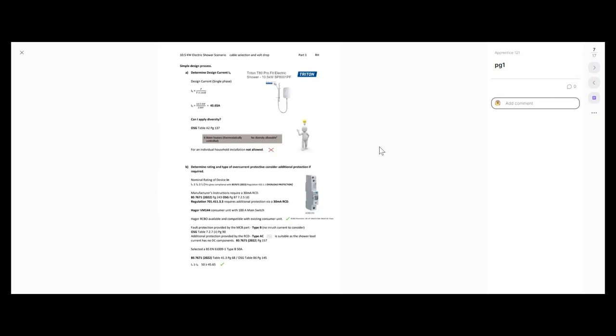So we can ask: can we apply diversity to this shower? If we look in the on-site guide within Table A2 on page 137, it gives us guidance on how we can apply diversity — based on the type of premises and the load. This shower is a thermostatically controlled water heater, that's what it does. Looking in Table A2, it is an individual household and we're not allowed any diversity. It's going to pull 45.65 amps — as simple as that.